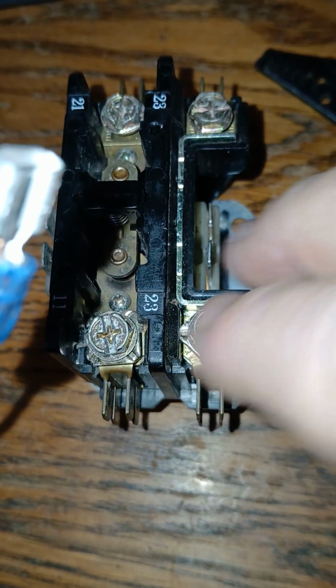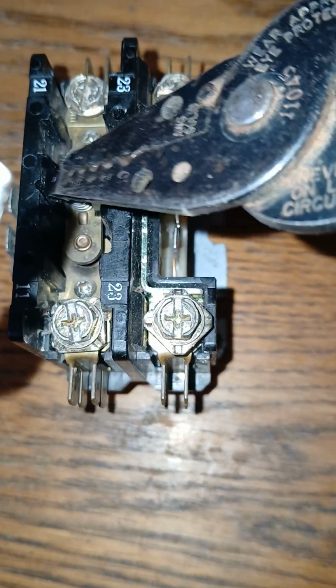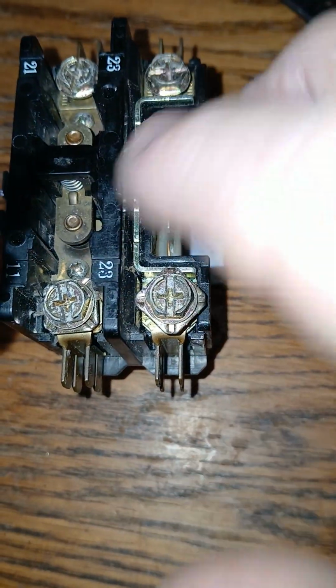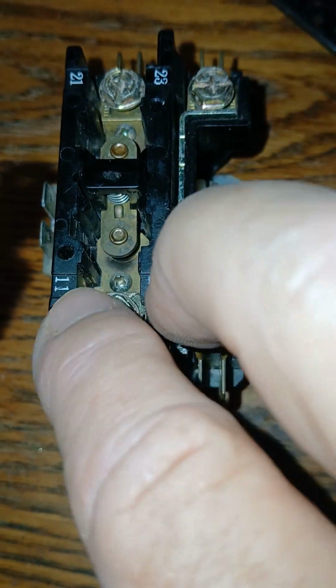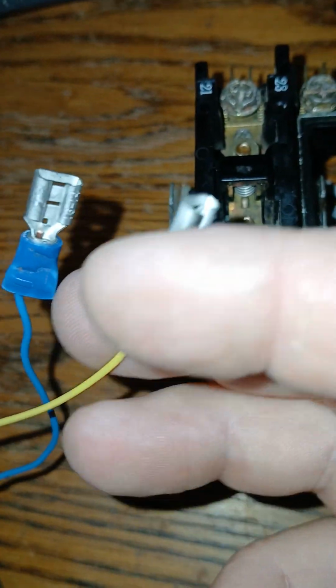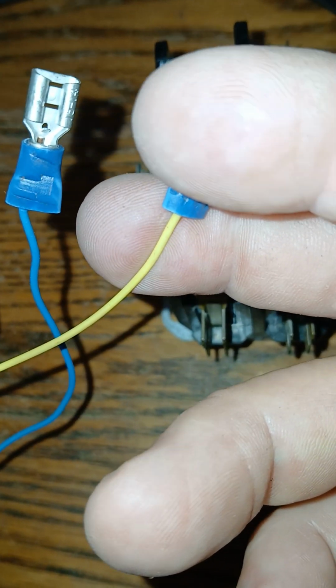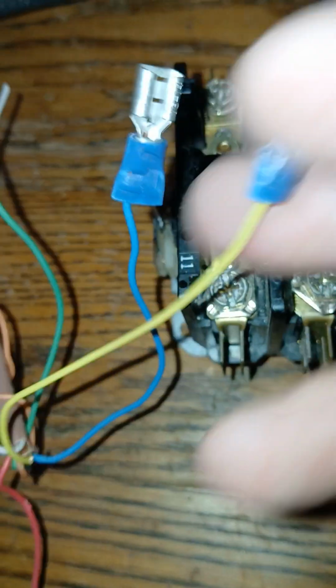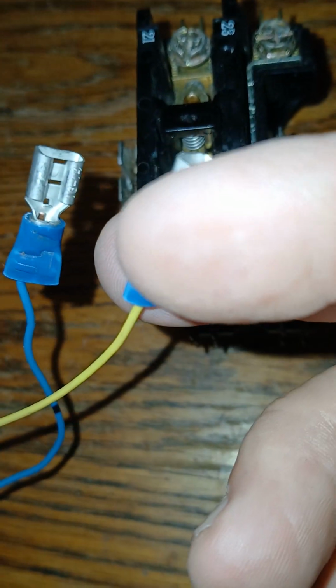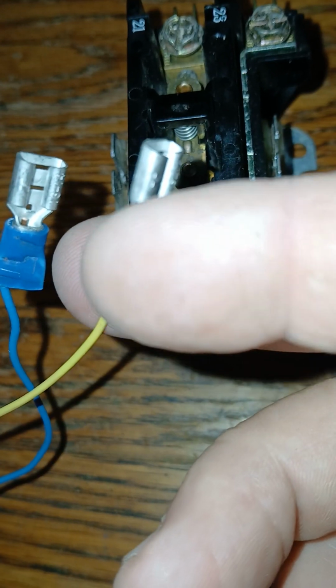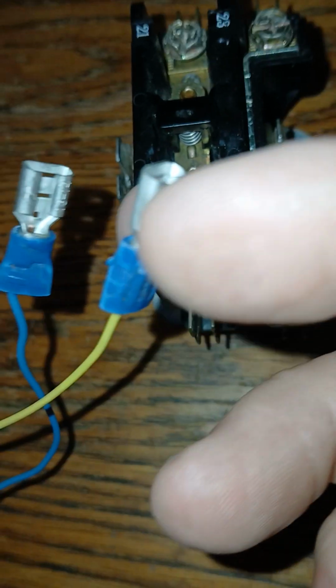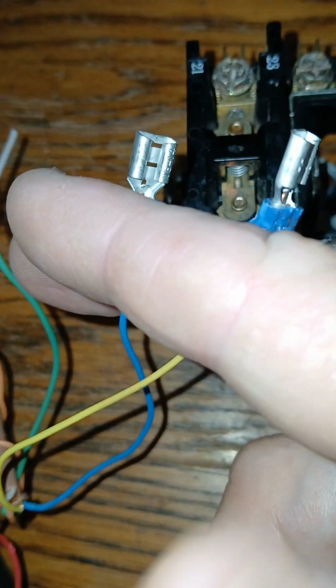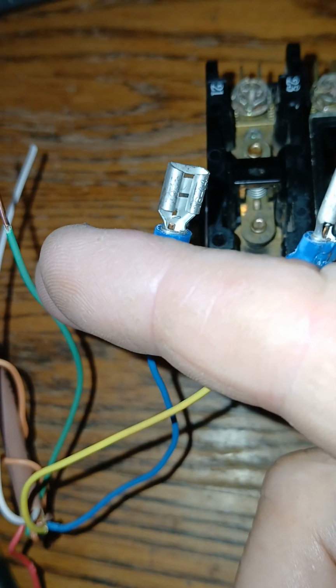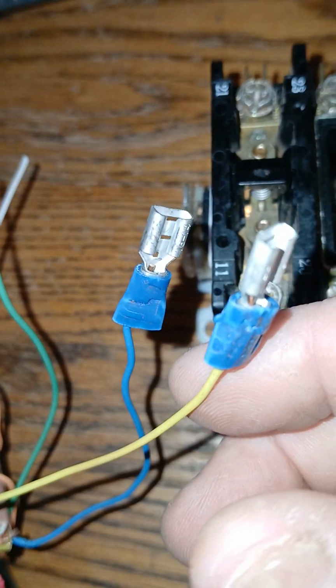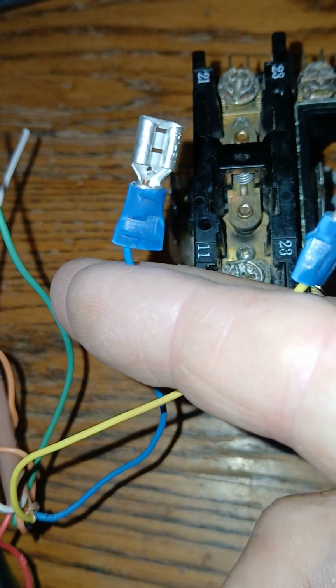So now the question here, as one can see on this contactor, it has the little pull thing. So the question, well, what energizes this to make this voltage jump here? It's actually low voltage. So how could we get low voltage over here? Well, low voltage is 24 volts, say the thermostat wire. If we did it this way, now there may be another way to put a cap on here. And by the way, if the HVAC guys could put in the comments what's the best color to use for 24 volts, or one could use the stranded wire and put two of these onto the stranded wire and then tie the stranded wire to the solid wire. But if we went straight to it, we would have a hot for the condenser and a common.